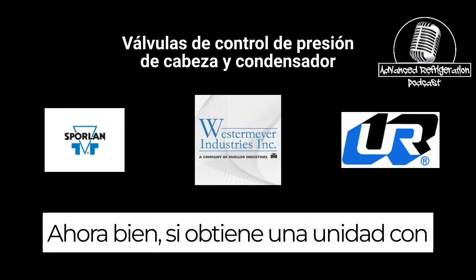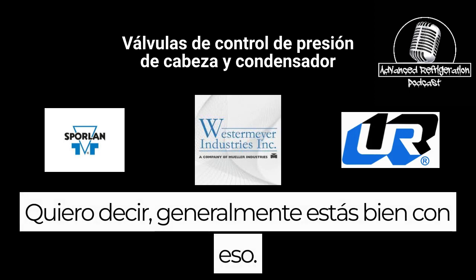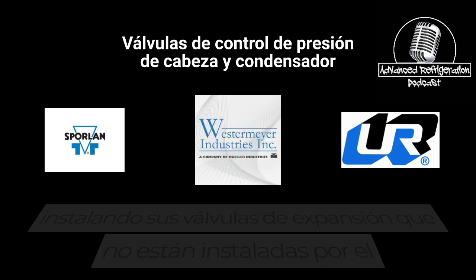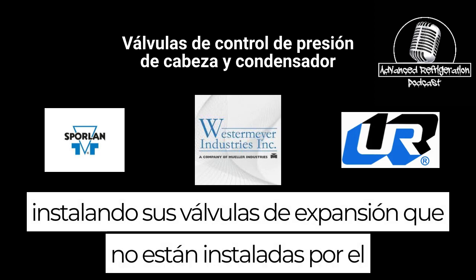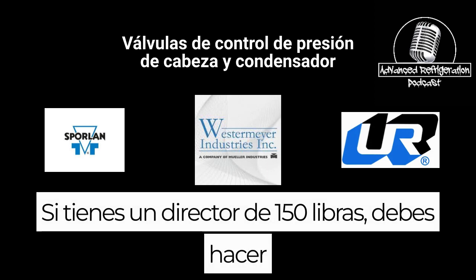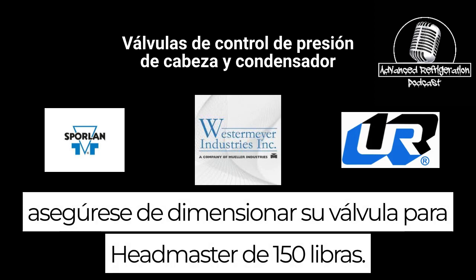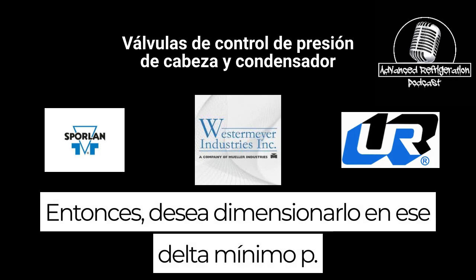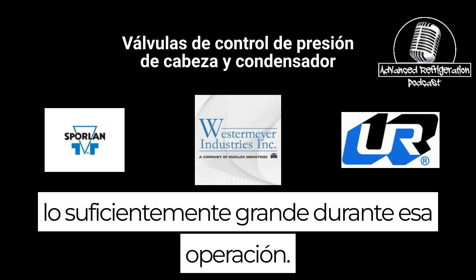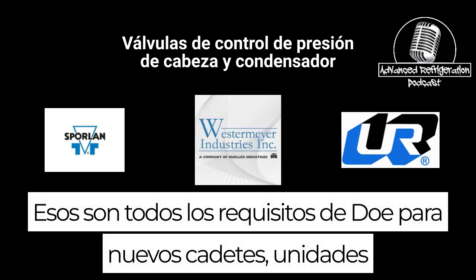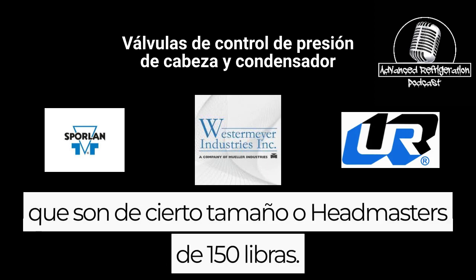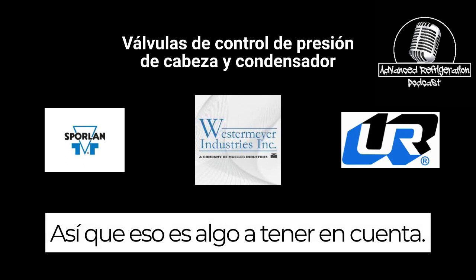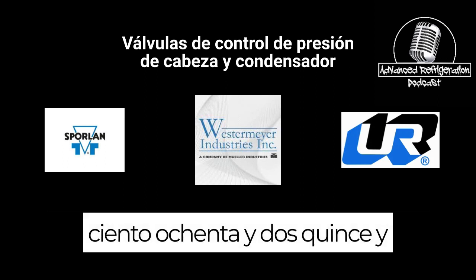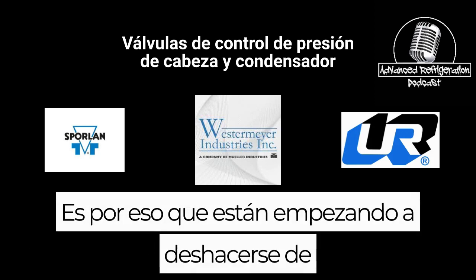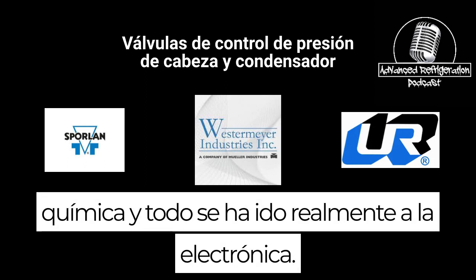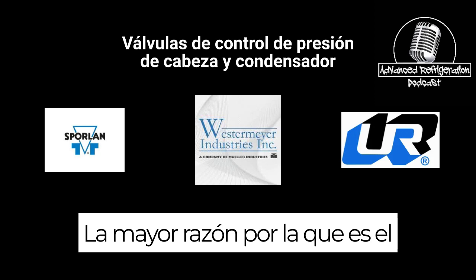Now, if you're getting a unit with a 100-pound headmaster and it's low temp, you're generally fine with that, but you also need to make sure, if you're installing your expansion valves and it's not installed by the coil manufacturer, that you look up there. If you've got a 150-pound headmaster, you need to make sure that you're sizing your valve for a 150-pound headmaster. So you want to size it at that minimum delta P, so that way your valve is big enough during that operation. That's all DOE requirements for new condensing units that are a certain size, or 100 to 150-pound headmasters. So that's something to keep in mind. You're going to start seeing some of these 180s and 215s and 210s go away on units. That's why they're starting to get rid of mechanical, and everything's really going to electronic. The biggest reason for that is the range of the electronic expansion valve.